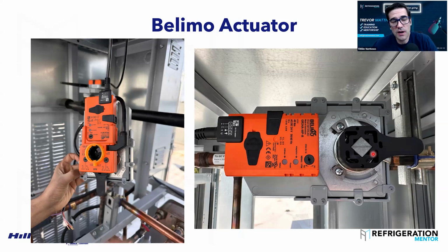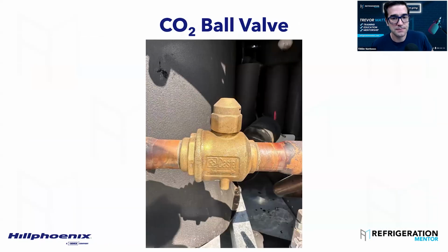And there's other ones that I've seen where if you have a three-way valve and you just have one heat reclaim coil, you do not want a deadhead. You know what I mean? All of a sudden you close your three-way valve going out to your gas cooler condenser, but your heat reclaim coil isn't open yet. Then all of a sudden you're going to go off in high pressure. That's one of the things that I've definitely heard from a lot of controls contractors, like the service technicians, saying if you're going off in high pressure, it may be the Belimo valves. Like maybe they stopped working, maybe they fell off. I've even heard contractors say I came in, they sent me a picture and the Belimo was hanging off the rack, so it vibrated off. You know what I mean? So this is something that you got to take a look at. Yes, sir.